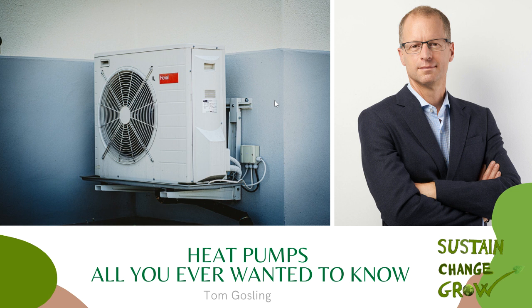The problem is that heat pumps work most efficiently when you're asking them to heat stuff a bit rather than a lot. So a heat pump will work much more efficiently if it's heating water to 40 degrees C than if it's heating it to 70 degrees C. And so, yes, you can use them for hot water, but that's one of the things that creates a drag on efficiency because we tend to want to have our hot water a little bit hotter than 40 C. And we've also come used to running our radiators extremely hot as well.